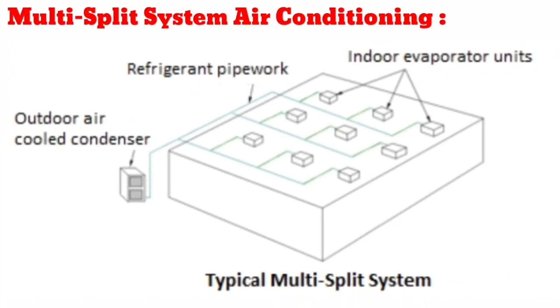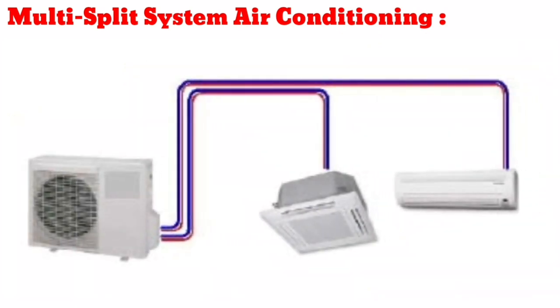Multi-split units are simply a large version of a small split, consisting of several indoor units — up to around 10 — connected to a single outdoor unit. Multi-split units are preferred if you do not want to install ductwork and if you want fewer outdoor units due to lack of outside space, or to preserve your building's external appearance. They are most frequently used in places like restaurants, offices, doctor surgeries, and shops.